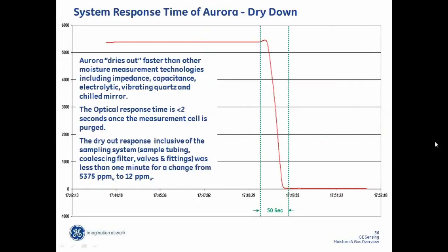This is just a graph that shows the system dry out. Here we have a step change from about 5,500 parts per million to 12 parts per million, and that step change occurred in 50 seconds, and that's inclusive of the sampling system and the volume of the absorption system. So by comparison to other technologies, this is much, much faster. It's magnitudes faster. If this same step change were aluminum oxide, it would take hours, or close to an hour, let's say, to fully stabilize at the same step change. A chilled mirror would probably take 30, 40 minutes, if not an hour as well.